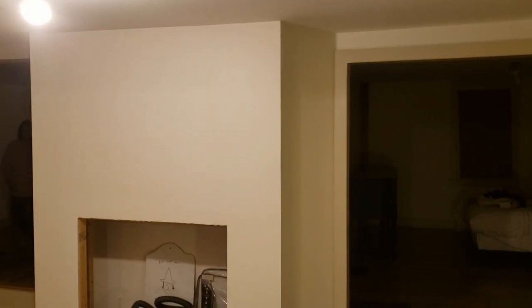Wonderful. So downstairs in the living room, in this corner, is where the helper fan is going to have its intake. It's going to be 2x10 with a 4-inch feed. That feed will come from underneath here in this corner, way up in the corner. This is the hole that was upstairs in the bedroom right here. So there's going to be a 4-inch hole here. It's going to connect to a boot. It's going to do a 90, to another boot that will be on the other side of this wall. That will work out just ducky, and I won't have to cut any of this beautiful framing.